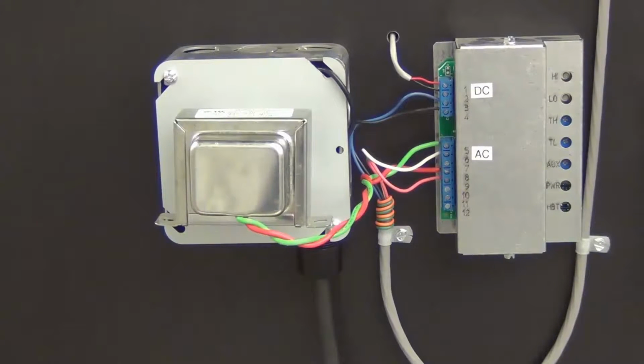Wiring connections shown in this installation are as follows. Power to the transformer, either 120 or 240 volt. Low voltage wire from the current transducer to terminals 1 and 2. Terminals 3 and 4 are low voltage DC to the EC supply fan. Terminals 5 and 7 are low voltage from 24 volt transformer.